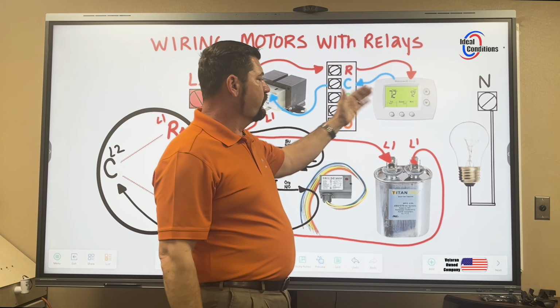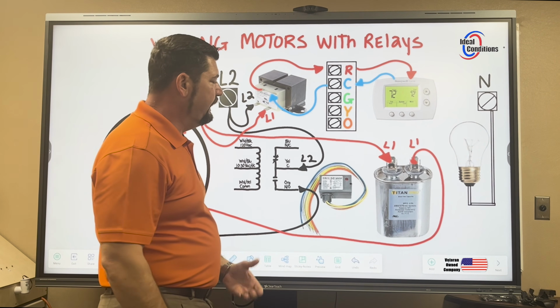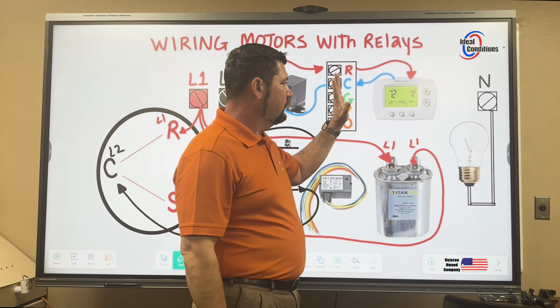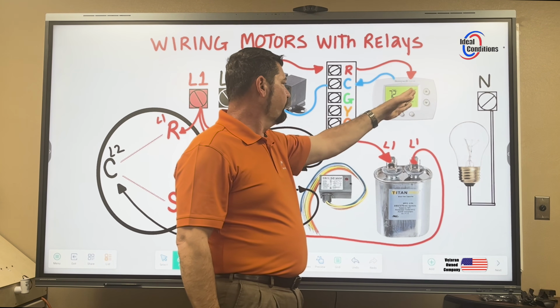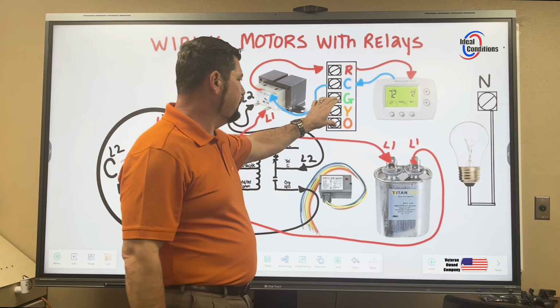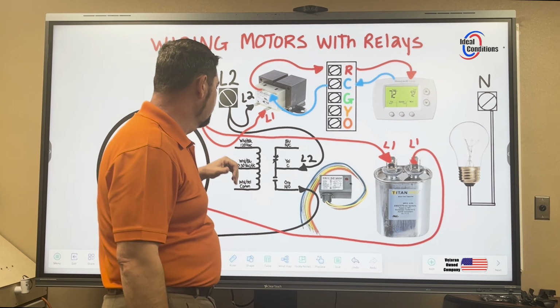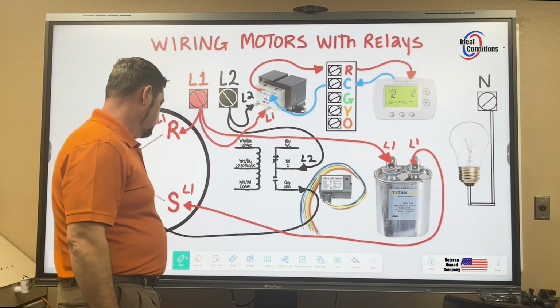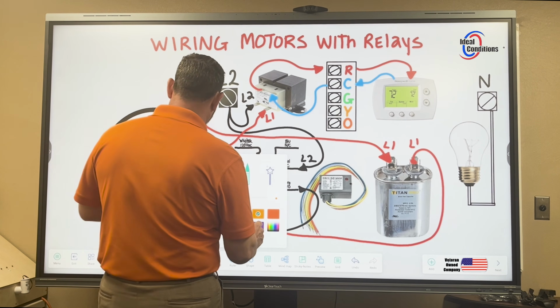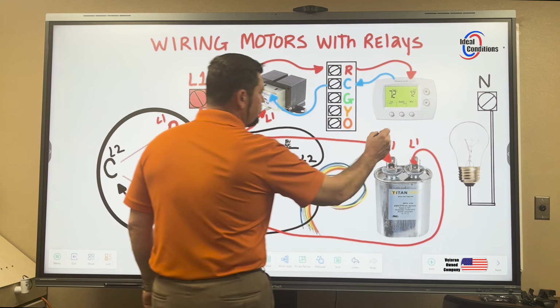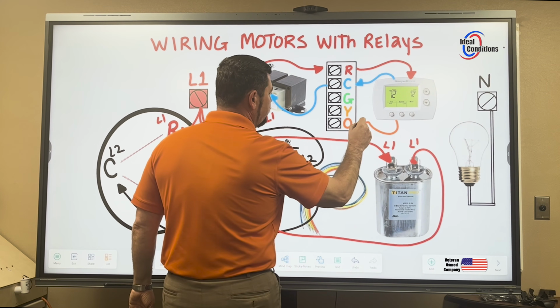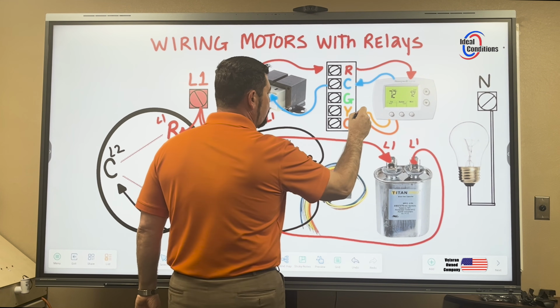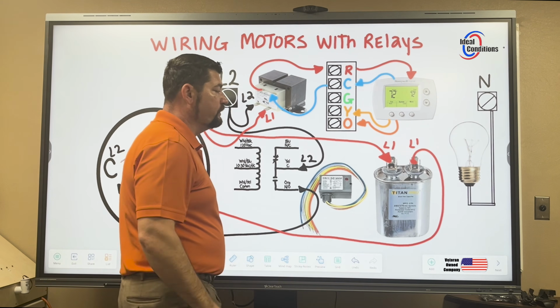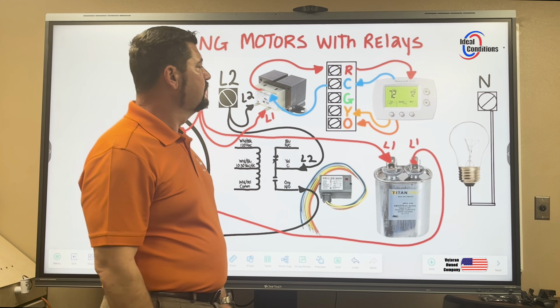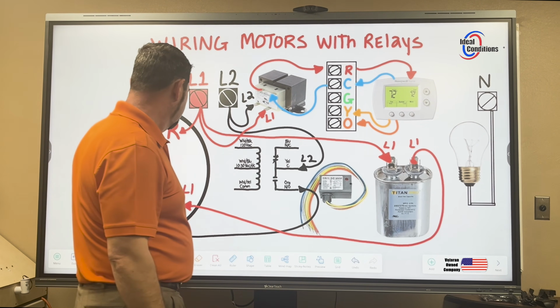And now whatever mode that this thermostat's programmed for heating, cooling, G-call, whatever, it's going to toggle 24 volts onto those terminals, and it's going to energize this terminal block, which then we can take power from here and run it to my coil voltage. We're going to come over and pick a couple of different colors. We're going to say that the thermostat provides 24 volts on O for cooling, and it provides 24 volts on Y for heating by itself, or to get the condenser to come on, we'll say. And then G is what we're looking for.